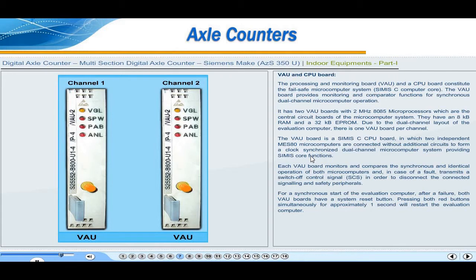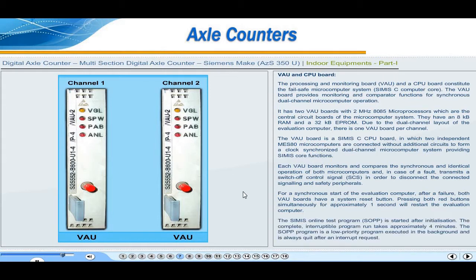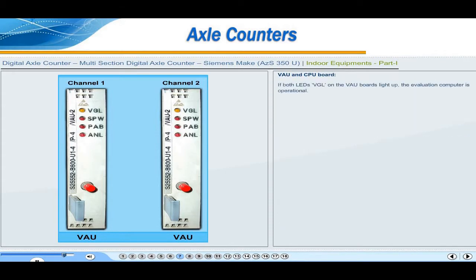The SIMIS online test program, that is SOPP, is started after initialization. The complete interruptible program run takes approximately 4 minutes. The SOPP program is a low-priority program executed in the background and is always quit after an interrupt request. If both LEDs VGL on the VAU boards light up, the evaluation computer is operational. A lit LED SPW indicates that the operating voltage is above or below the permissible value of 5 volt DC. Then the system has to be restarted.